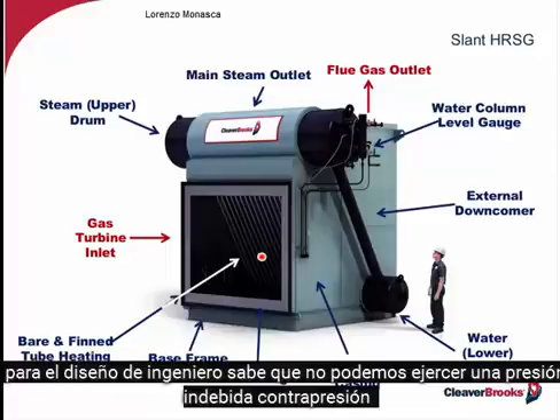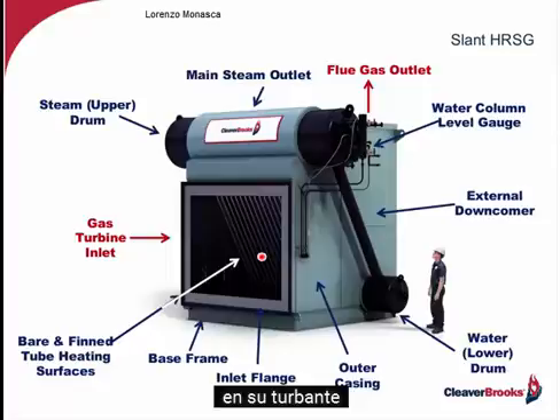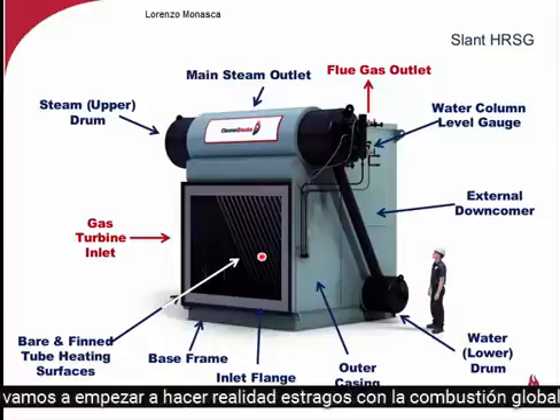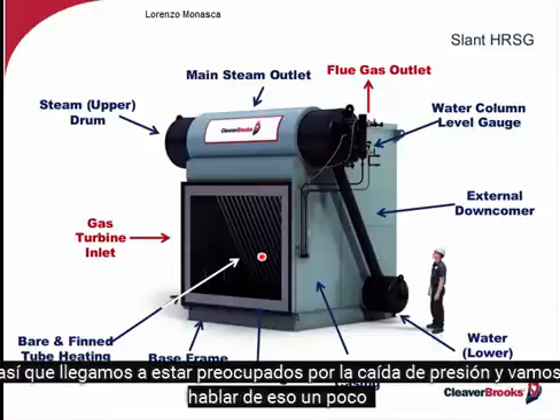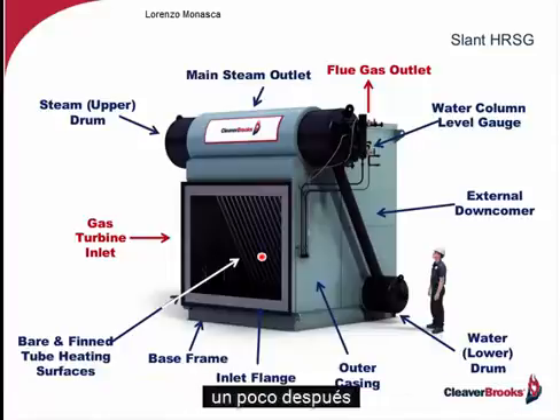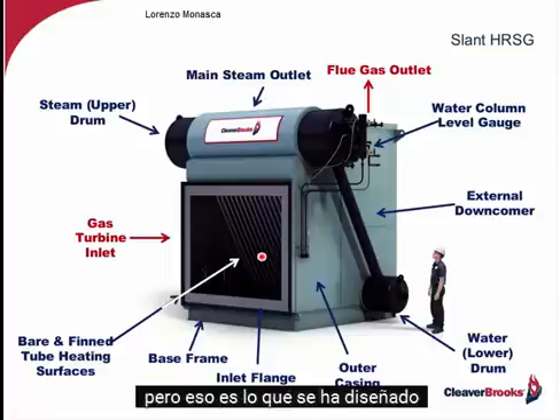But the design engineer knows that we cannot put undue back pressure on that turbine, or we're going to start to really cause havoc with the overall combustion. So we've got to be concerned about pressure drop, and we'll talk about that a little bit later. But that's what's been designed.